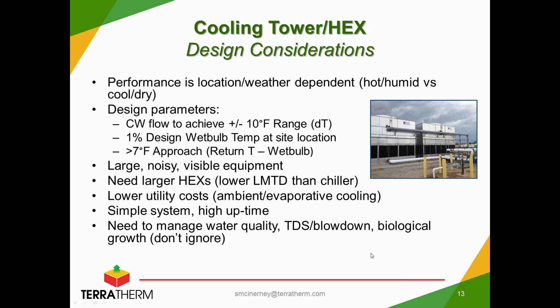So I'm not going to get into the cooling tower design considerations in a lot of detail here, but really, we're talking about a weather-dependent system. Where you situate this equipment will dictate the quality and the temperature of your cooling water. Hot and humid locations are much worse than cool, dry locations in terms of just how much heat exchange you could expect through these devices.